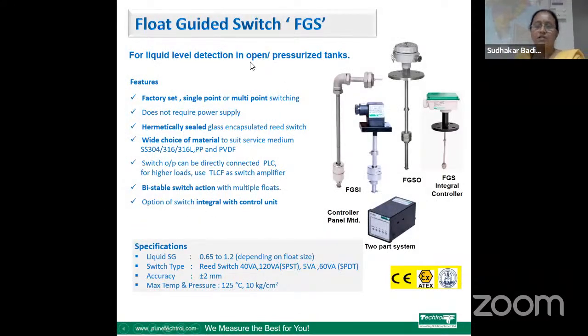This is a float guided switch. This is used for level indication in an open or pressurized tank. It is a factory set switch, and it is available with single point or multi-point switching contacts. This does not require a supply. The reed switches are hermetically sealed, encapsulated in glass. A wide choice of material is available in various grades of stainless steel, and PP and PVDF. The switching output is potential-free reed switch contacts, which can be directly connected to a PLC. However, for higher loads like motors or solenoid valves, we have controllers or switch amplifiers which can be used.